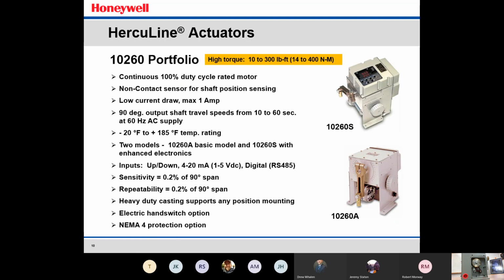The model above it on the slide here is a 10260S, and that's a smart 10260. It still has all the same features as an A, but it also has the availability to put a display on the top of the actuator where you can configure the stroke, configure the low and high end stopping positions, calibrate the actuator, and also see diagnostics and true position indication feedback on the display itself.